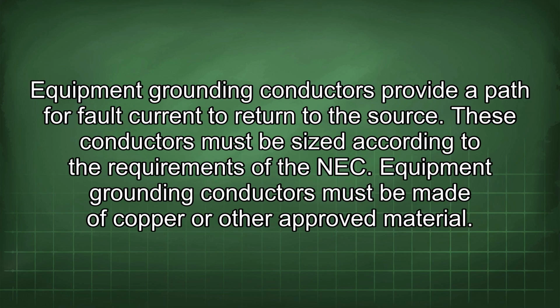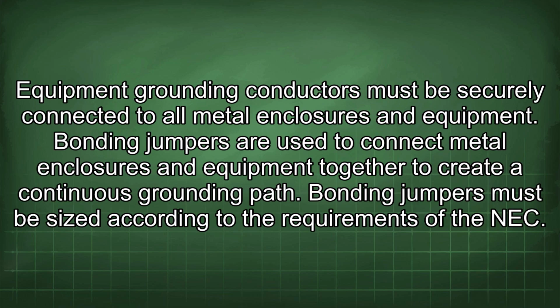Equipment grounding conductors provide a path for fault current to return to the source. These conductors must be sized according to the requirements of the NEC. Equipment grounding conductors must be made of copper or other approved material. Equipment grounding conductors must be securely connected to all metal enclosures and equipment.